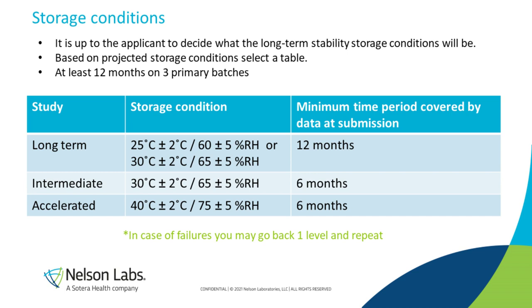Based on stress testing and expected storage of the product, we select one of three storage options: long-term, intermediate, or accelerated. The last column has the minimum time point needed for data before submission to the regulatory agency — this is just a minimum, and we would normally test through at least 12 months on the three batches. If there are failures, you can go back to level one and start over. This table is for ambient storage; if using refrigerated or frozen storage, you would store at your intended conditions for 12 months at a minimum.